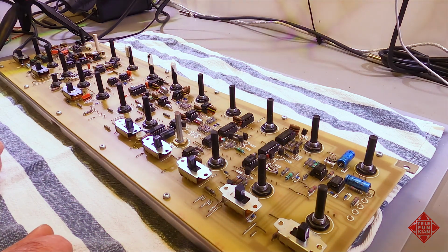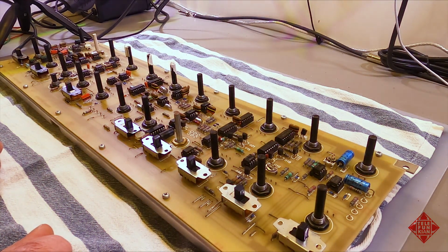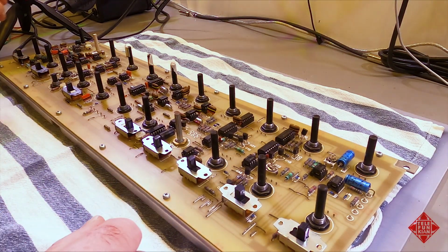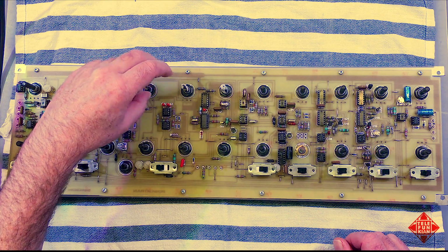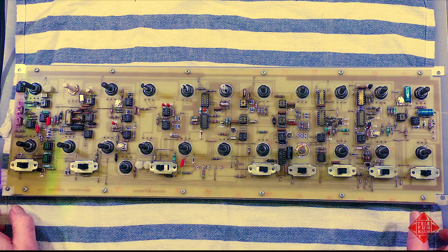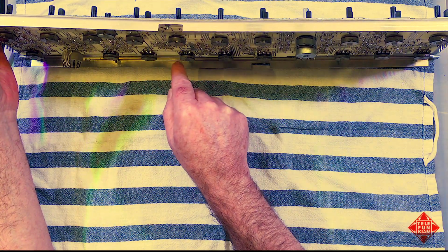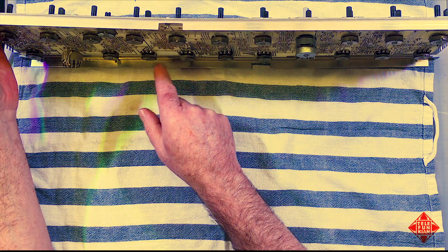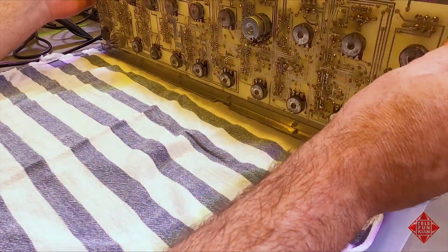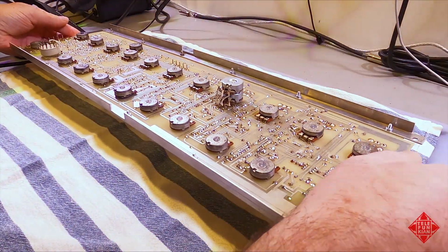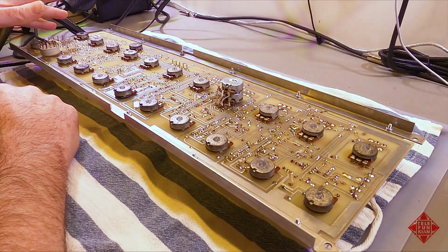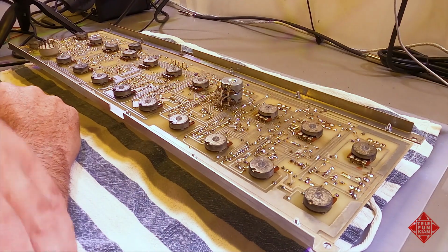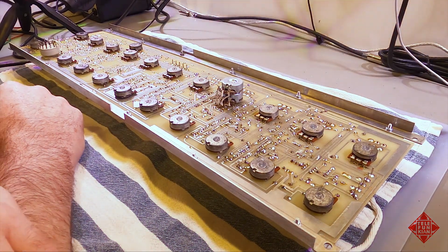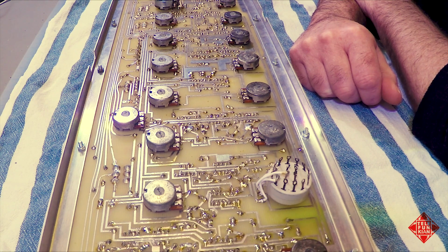We may replace some of those with multi-turn trimmers that will be a lot easier to use to calibrate the instrument. In addition, we have a number of potentiometers that I've indicated with masking tape on their shafts, which need to be cleaned. You can see we can spray contact cleaner into them from this direction, but it's a lot easier to make sure that's done properly with the board out of the instrument. There's also a tremendous amount of flux remaining on the board from its original assembly, and I'd like to clean all of that off. Again, that's something that'll be a little easier with the board out of the instrument.